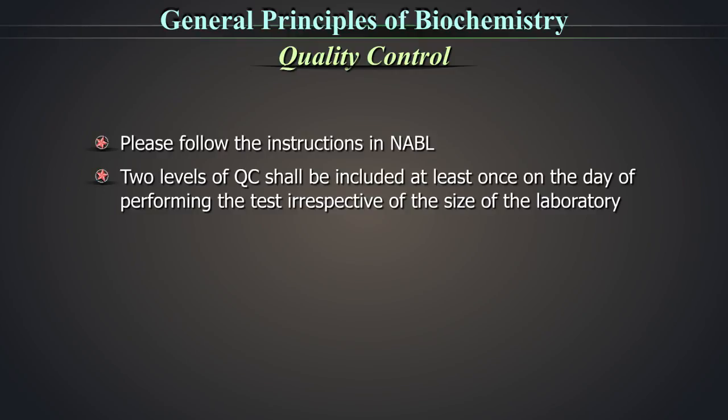Quality control. We already talked about QCs along with calibration verification. Here are some more details. Please follow the instructions in NABL. Two levels of QC shall be included at least once on the day of performing the test irrespective of the size of the laboratory.